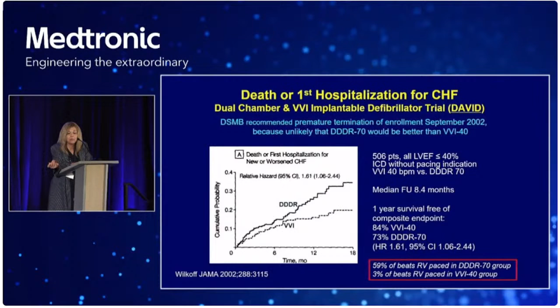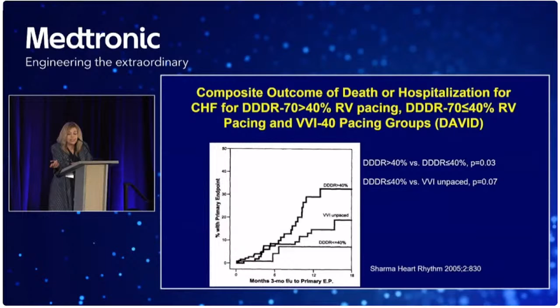In this case, you could see here that with dual chamber devices compared to VVI backup at 40 beats per minute, the time to hospitalization for new or worsening heart failure was shorter in people who were dual chamber programmed than VVI. And they tell you too that 59% of the beats were RV paced in the dual chamber group, compared to only 3% in the VVI group. So dual chamber pacing was not good. Pacing the RV was not good. And if you divide up, what percentage of pacing do you need? If you look at people who were paced over 40% of the time, those were the people who did worse. If you had dual chamber programming and you still rarely pace, that was okay. Or your VVI pacing and you rarely pace, that's still okay. But really you don't want to pace more than 40% of the time.